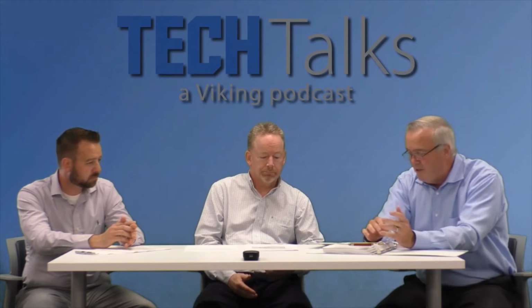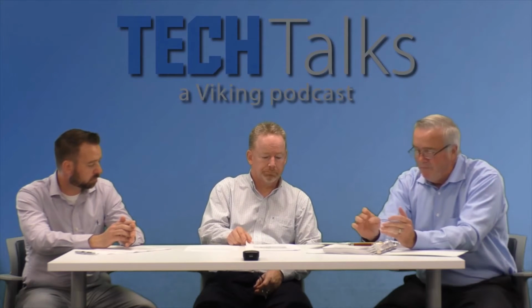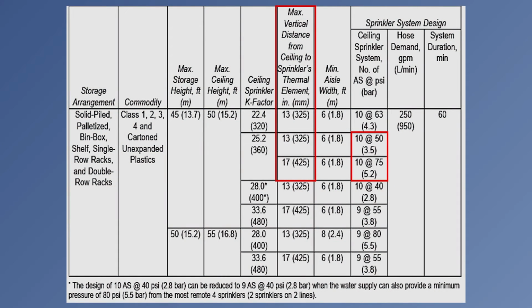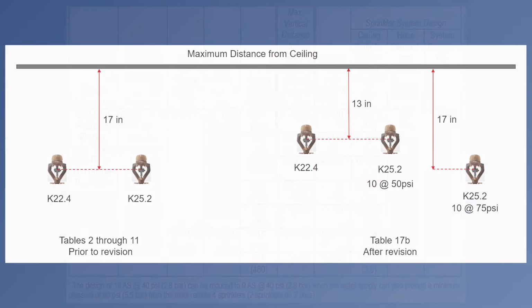So two things to consider that are right off the bat is the deflector distance is now going to have very specific criteria in Table 17B as compared to Tables 2 through 11, where it was a default. Any K22 or K25 or larger had a 17-inch operating element deflector or a distance from the ceiling criteria.